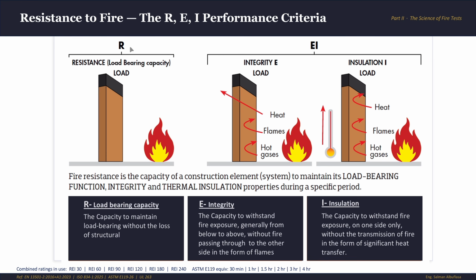Resistance to fire: the R, the E, and the I. What do they mean? First, resistance, or the load-bearing capacity, which means the structure keeps holding its weight, no collapse. And then we have the integrity, which is written as E, meaning no flames, no hot gases pass to the other side. And finally, the insulation, meaning the unexposed side stays cool enough that nothing ignites from heat transfer alone. The limit is a 140 Celsius average rise.